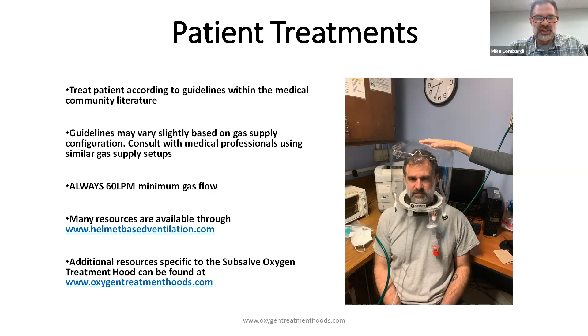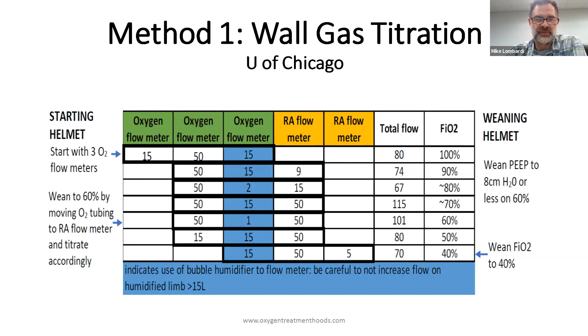So I'll just very, very briefly walk through a few methods that are commonly used. This is courtesy Dr. Patel, and I'll let her explain it in more detail, but illustrates that there is a method to supply the hoods with wall gas titration, meaning you have multiple air and oxygen supplies introduced into the hood at various flow rates to achieve the desired FiO2 and pressures in the hood. There's another method, this one is used by Penn Medicine, and they call it their Venturi method. So again, this is a function of the devices supplying the hood itself. They reference a few there, the Max Venturi unit, oxygen blenders, and so on. So if your particular institution favors these delivery methods, you would want to review Penn Medicine's guidelines carefully.